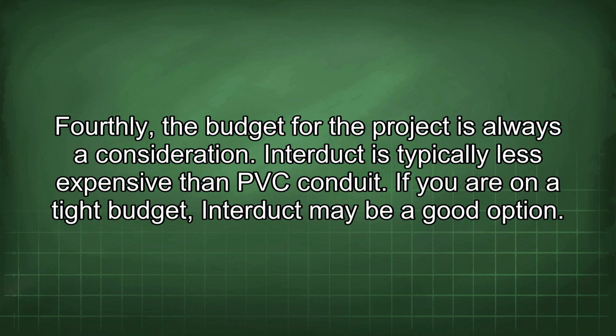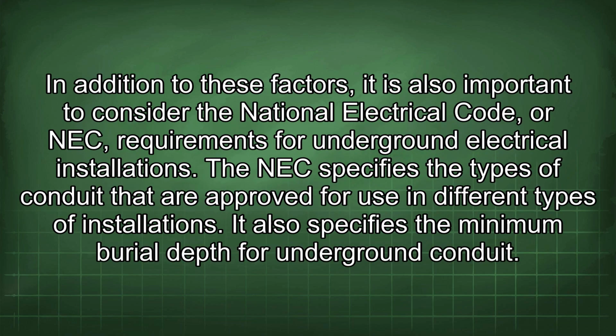Fourthly, the budget for the project is always a consideration. Interduct is typically less expensive than PVC conduit. If you are on a tight budget, Interduct may be a good option. In addition to these factors, it is also important to consider the National Electrical Code, or NEC, requirements for underground electrical installations. The NEC specifies the types of conduit that are approved for use in different types of installations. It also specifies the minimum burial depth for underground conduit.